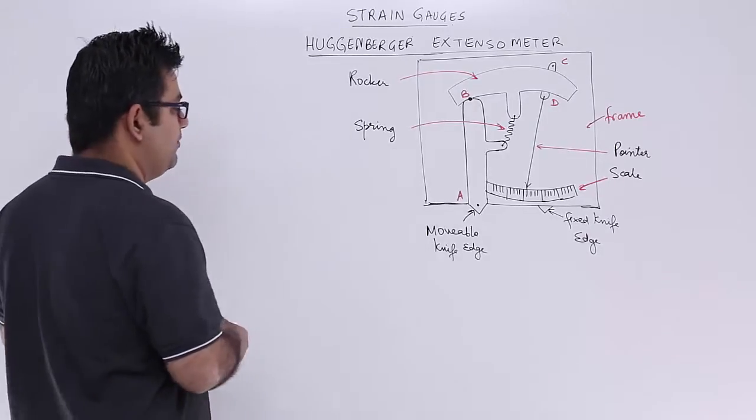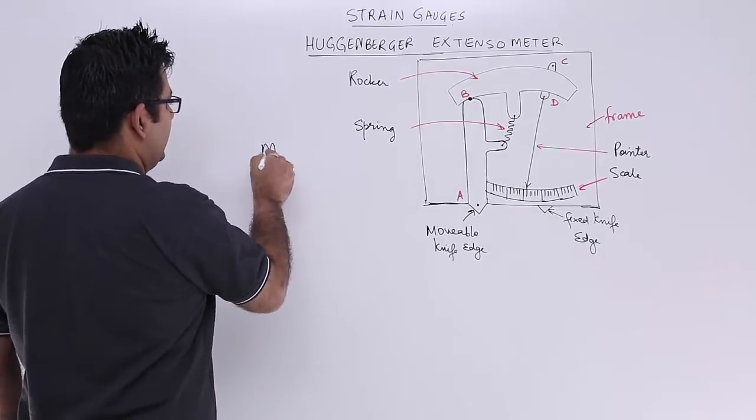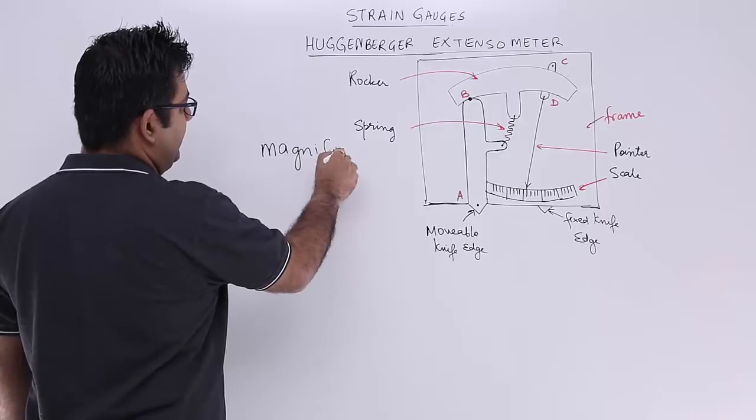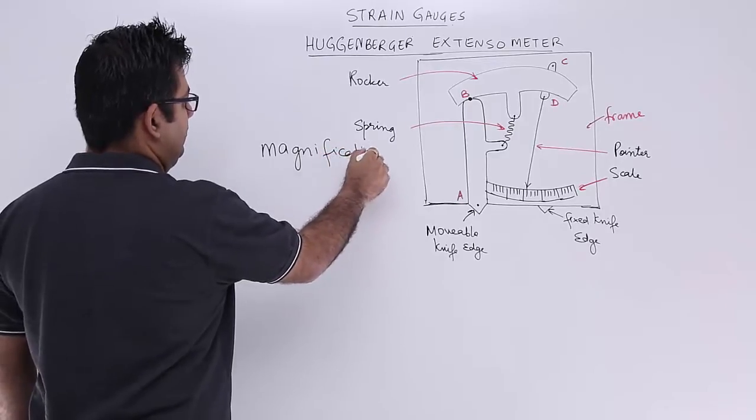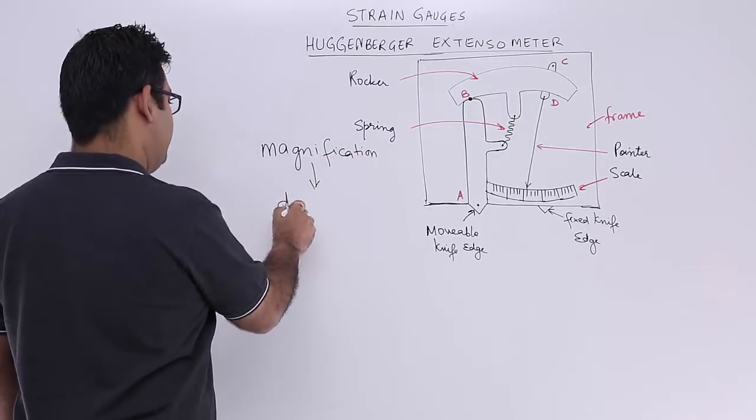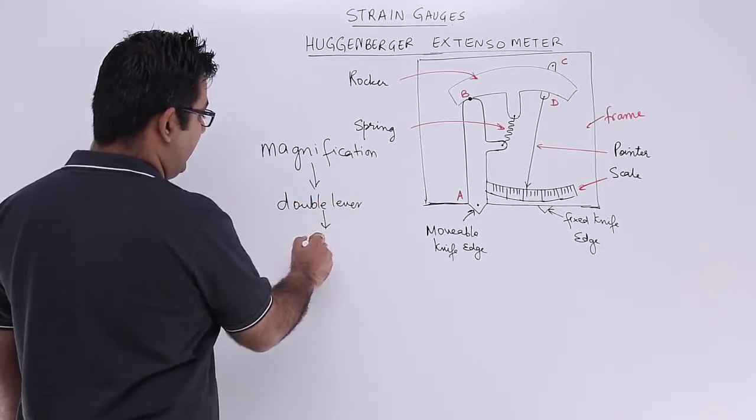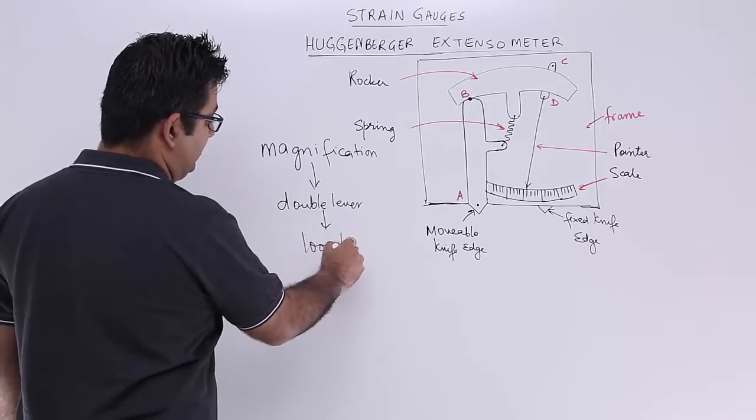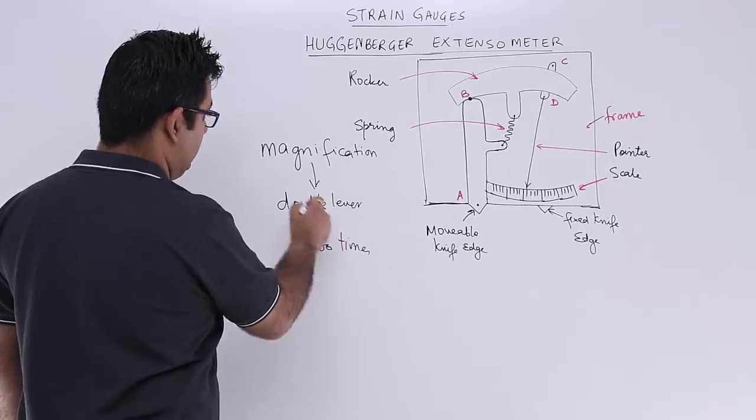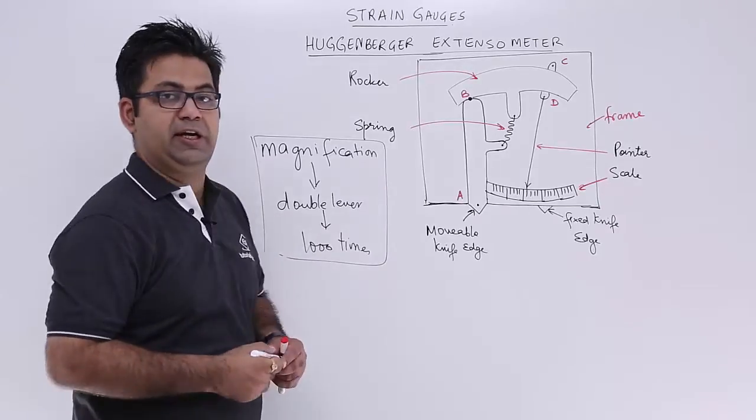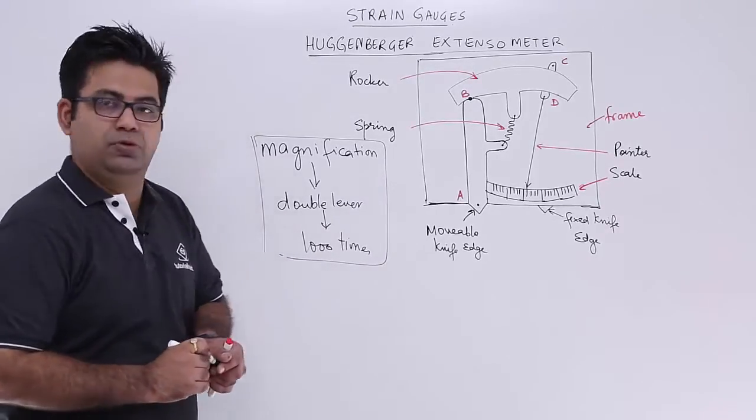So in this the magnification is basically brought about by using a double lever mechanism. We make use of a double lever mechanism and the magnification is about 1000 times. So this is how good it is as compared to the previous two extensometers.